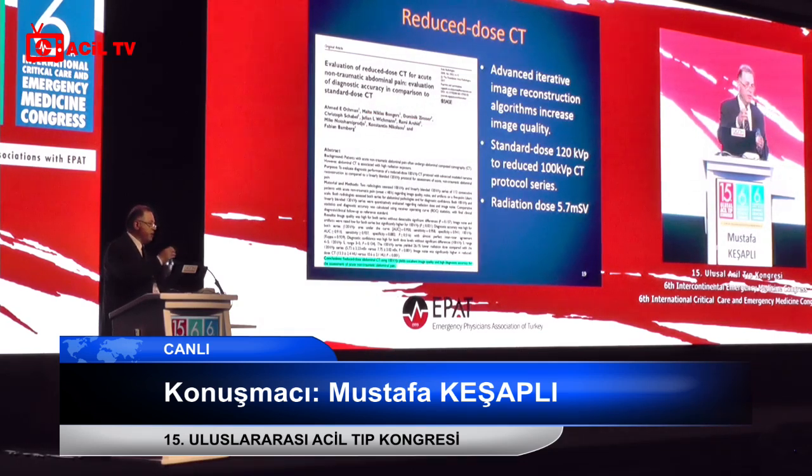Some of the mechanisms, some of the recommendations to reduce the effect of the radiation, is to reduce the dose of CT. I mean, most CT machines are using a 120 kilovolt energy level of radiation. So if you reduce this energy to 100 or maybe 80, it will be much less radiation exposure to people. In some papers, for example, they reduced the energy level from 120 to 100, and the radiation dose was approximately halved.